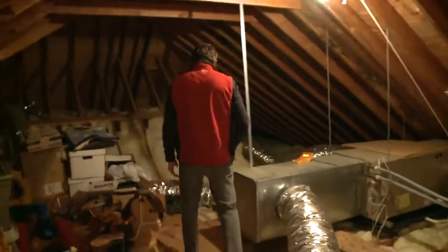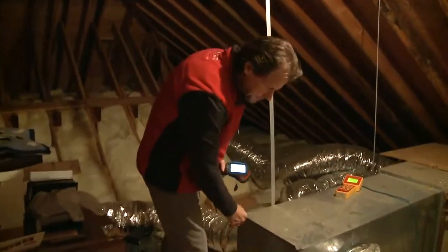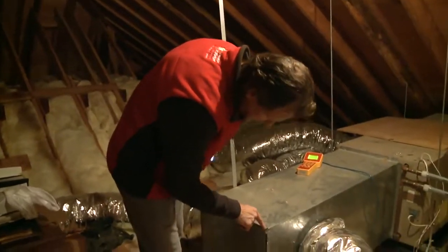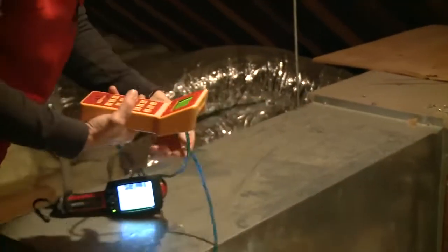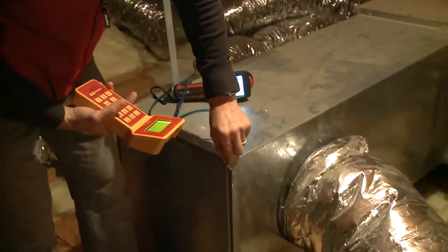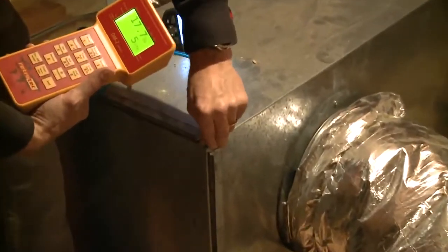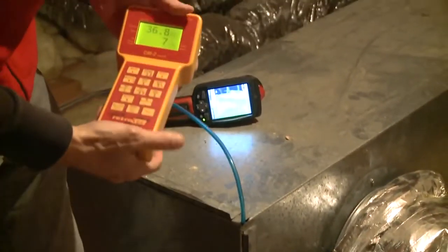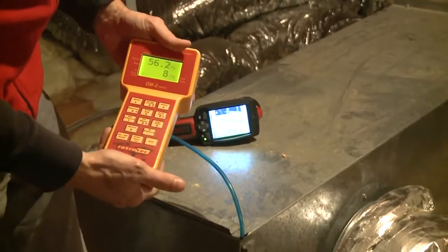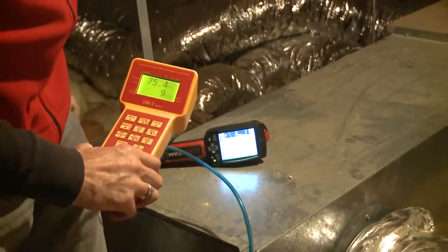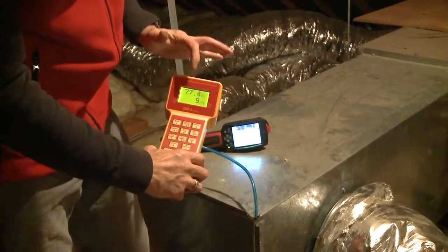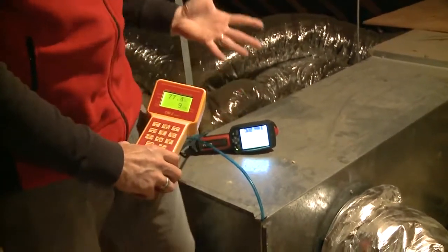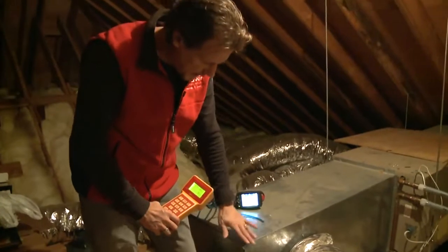And let's go over here. And we see that these ducts are not sealed. I mean, it's just sheet metal bent together. I mean, look at here. Here's a big hole. Here's a hole in the duct. And if I stick this tube in that hole, let's see how many pascals difference that is. Wow. These are the biggest pressure differences and temperature differences that we will find in a house. 77 pascals of air pressure pushing air out of this hole.